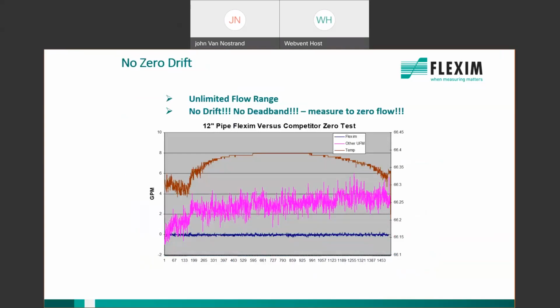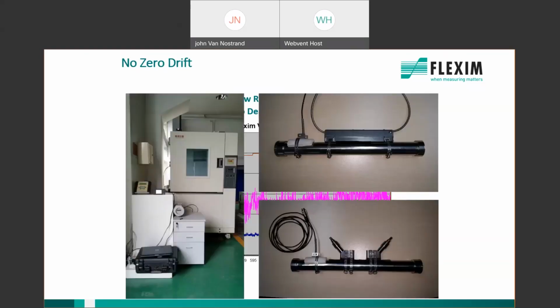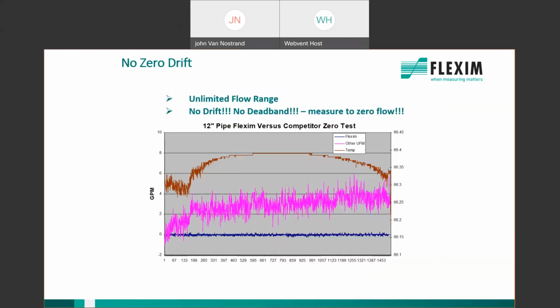So here's what happens when the transducers are not compensated. What we're looking at here is a FLEXIM transducer shown in blue, and a competitor transducer shown in magenta, and then the brown shows just the temperature overnight. All we did was clamp on a piece of pipe with the transducers mounted on it and leave it overnight for a period of time, and this is the result. We saw drift in the measurement from our competitor. And this is because of not having the temperature compensation circuit.